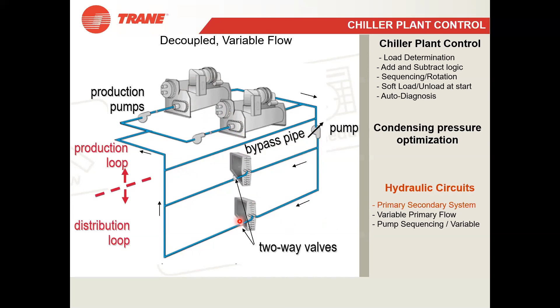Decoupled variable flow. So what is that actually? By using this CPC, we are putting a temperature set point here. Okay, this is the return water temperature. This is the supply water temperature. And this is the line where I have put a flow meter. This is the bypass line actually. So there I have put a flow meter, so all the time I'm monitoring the flow. All the time I'm monitoring the temperature of return water and supply water. So what will be happening?